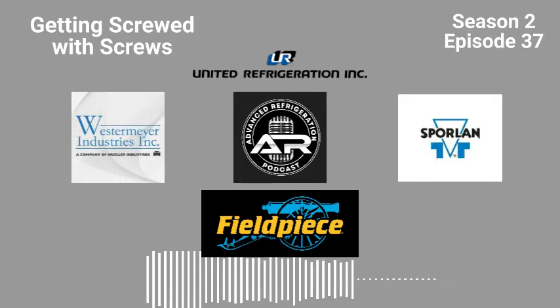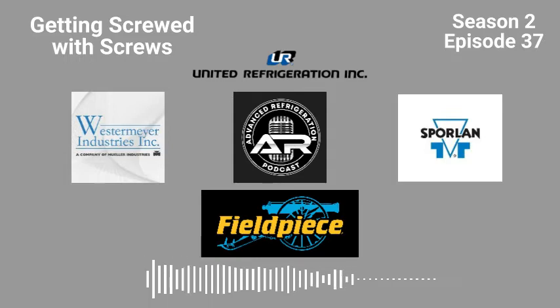Didn't you just say you're doing a startup on it? Yeah, they just added a ton of load. So basically the oil's trashed. But usually with the screws, you start up with a cleanup procedure. Generally, the oil filters catch everything in those things, because they're moving so much oil through them. So what we're doing is every morning, the service guy gets there and changes the filters.